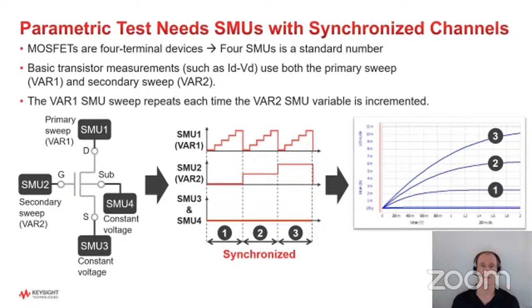In parametric tests, I want to point out that 4 is kind of a magic number, because we generally recommend that you have at least 4 SMUs if you're going to do general purpose characterization. Why is that? Transistors, as shown here, for example a MOSFET, are generally 4-terminal devices. People sometimes forget that there's not just a drain, gate, and source, but also the substrate connection. That's very important because the voltage on the substrate will affect the results you get from the other types of measurements. It's also very important to have the SMUs all synchronized with each other, for obvious reasons. You want the measurements working together, and everything has to be timed correctly. So again, this is very important in parametric tests: 4 SMUs that are completely synchronized with each other.